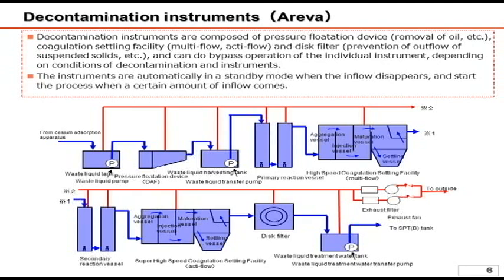Page six describes the entire system. While the material describes the system with two layers, each layer essentially has the same function. First, the water processed by Curion's cesium adsorption apparatus goes through an oil removal process. Afterwards, chemicals are injected into the water in the primary reaction vessels. The chemical reaction between the chemicals and cesium is enhanced in the high-speed coagulation settling facility, multi-flow.